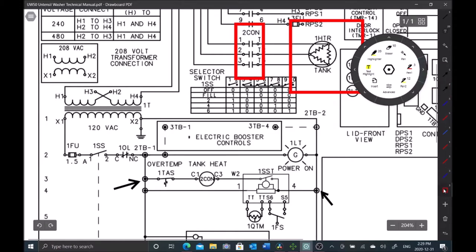So the next place where I'm going to test is going to be at this point here and this point here. So what that is is 2TB1 which is terminal block 1 and terminal block 2. By testing that it's going to tell me if the transformer is good and everything before the transformer.